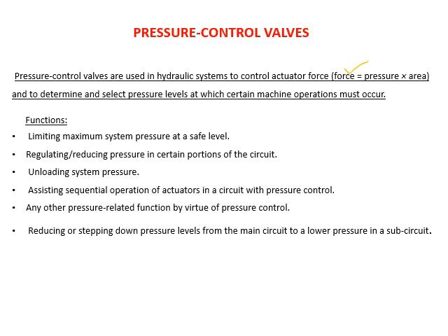So it has some functions, like limiting maximum system pressure at a safe level in the circuit, then regulating or reducing the pressure in a certain portion of the circuit, then unloading the system pressure, then assisting sequential operation of actuators in the circuit with a pressure control. Any other pressure related function by virtue of a pressure control is achieved with the help of pressure control valves, as well as reducing or stepping down the pressure levels from a main circuit to a lower pressure in the sub circuit.